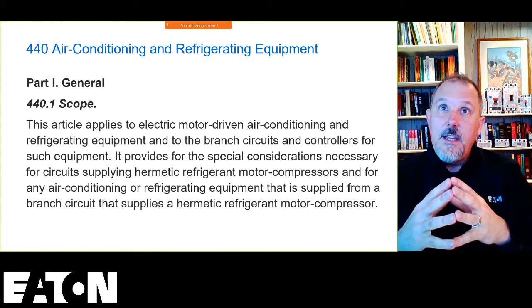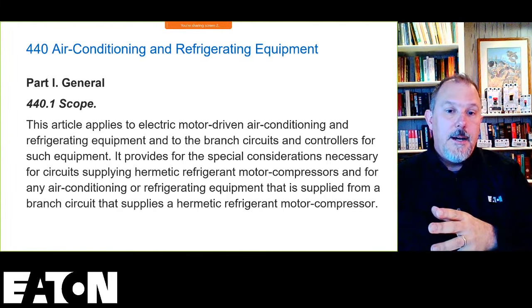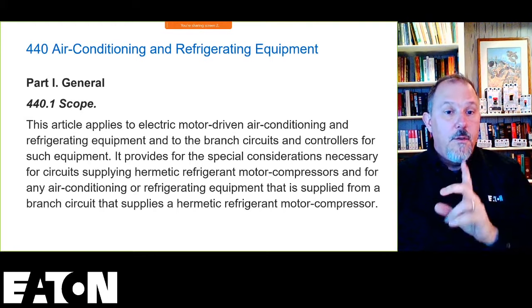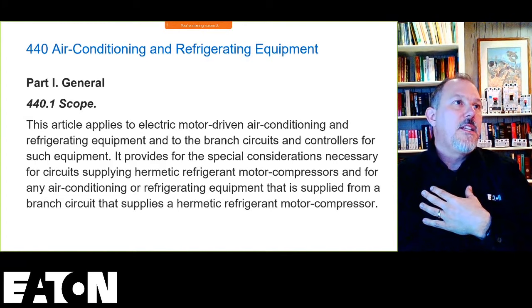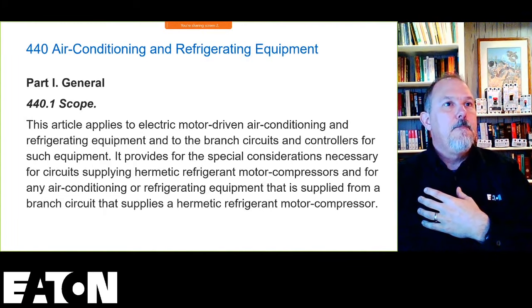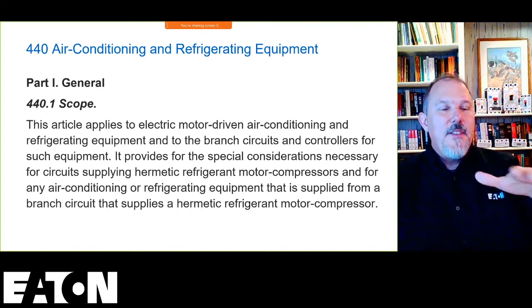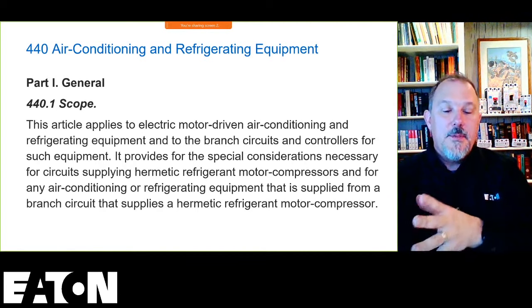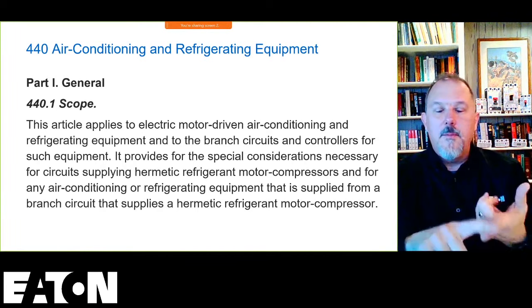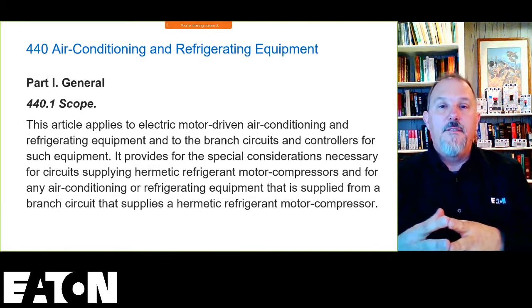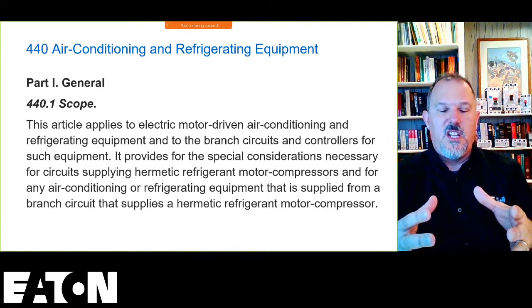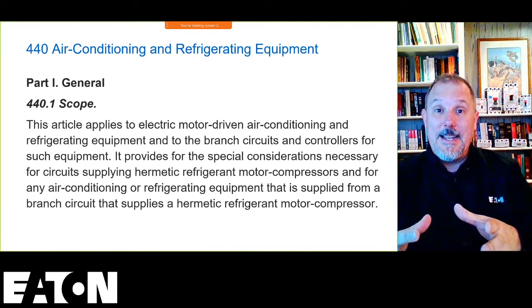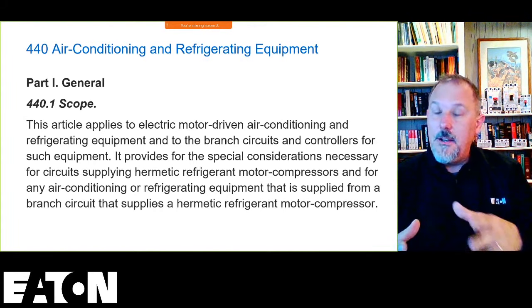Now, I would love to get others' feedback on this. As I navigated Article 440, it can be confusing. At least it was confusing to me, and I spoke with a few other people about this. As you navigate 440, this unit is a piece of equipment that's listed. It has a minimum circuit ampacity, it has a maximum overcurrent protection, so it's giving you that information. There's a lot of stuff in 440 that is necessary when things aren't as clean cut as this unit is, and I can really get lost in 440 trying to figure out some of the requirements.